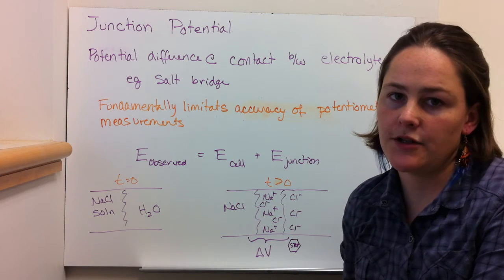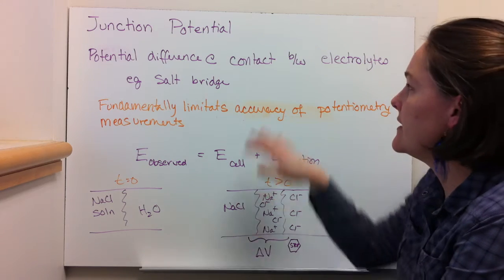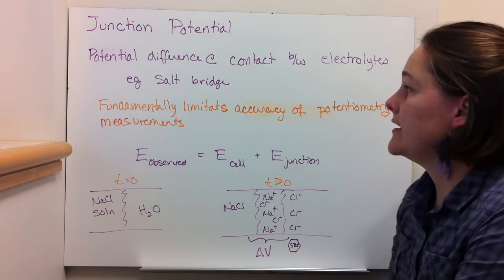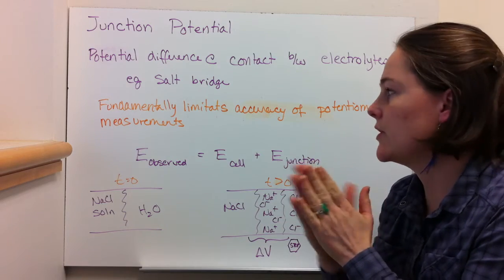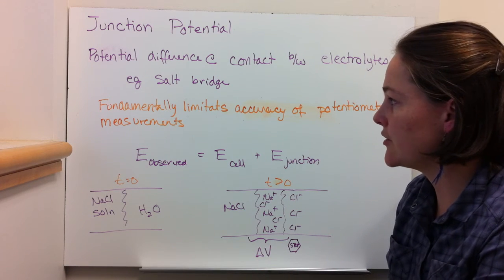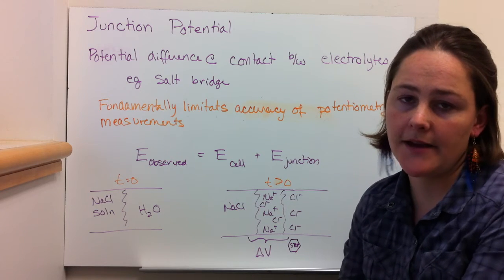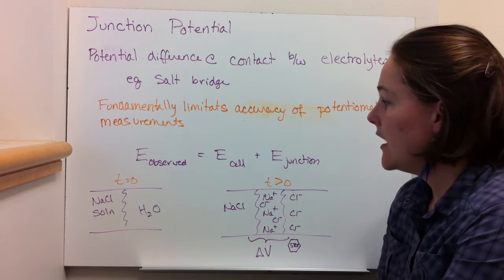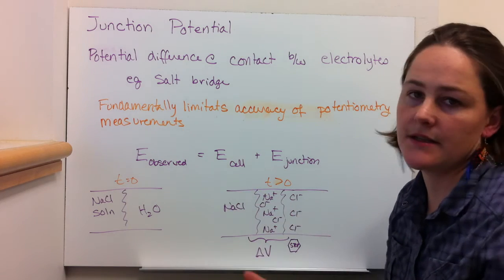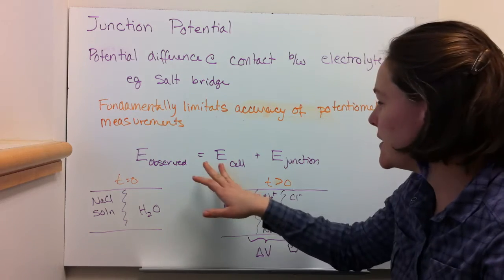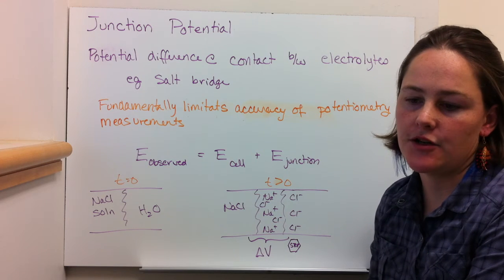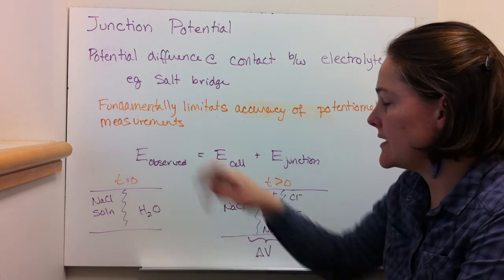The last thing I wanted to talk a little bit about is a junction potential. This is a potential difference that is generated when you have two electrolytes in contact, something like a salt bridge where you have two electrolytes in contact. Across each side of the salt bridge you can have one of these junction potentials. And this is what actually fundamentally limits the accuracy of potentiometric measurements. Because E observed, what you measure on your meter, is equal to the E of the cell plus the junction potential. And you can't often measure the junction potential, so you don't really know what it is. And that's why it's fundamentally limiting the accuracy.